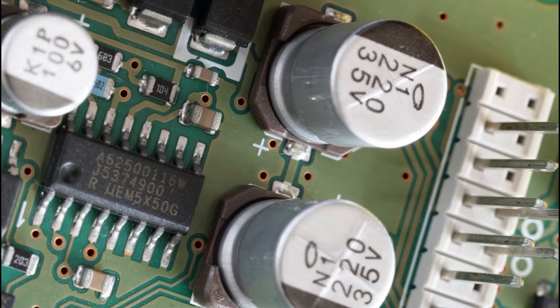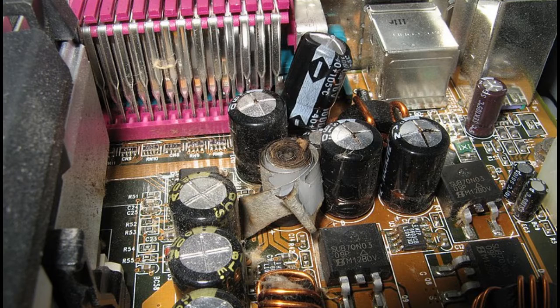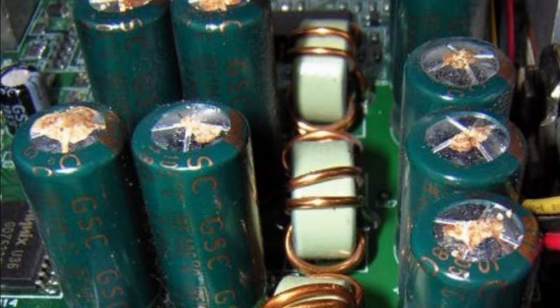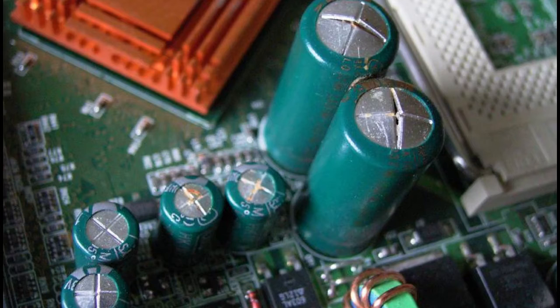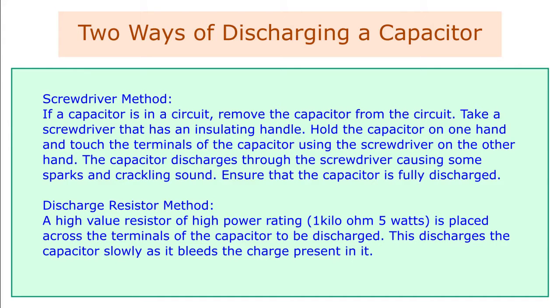For testing a capacitor, it must be taken out of the circuit and discharged before it is being tested. This is because of the high static voltages or charges collected between the plates of the capacitor. There are mainly 2 ways of discharging a capacitor, and they are as follows.